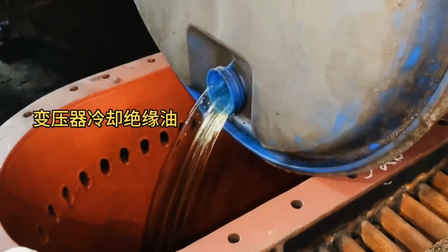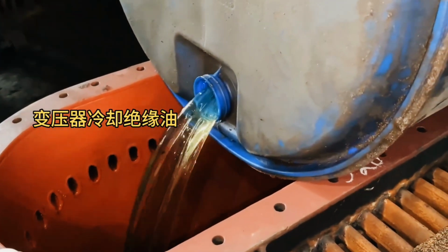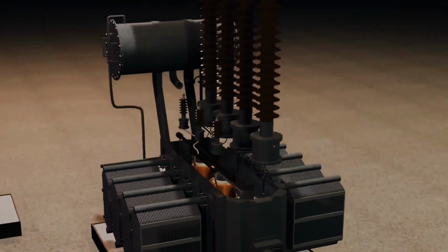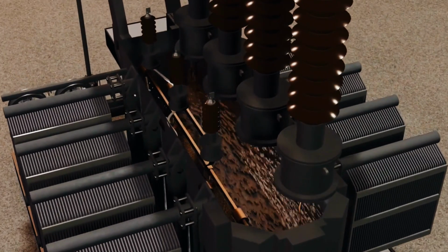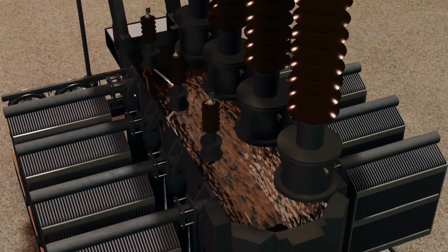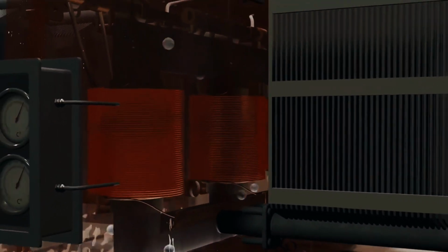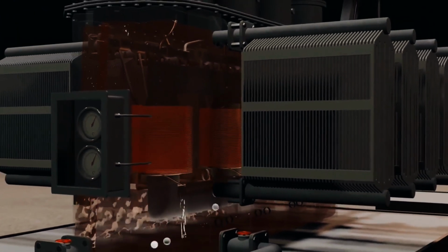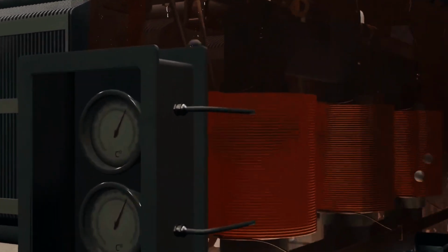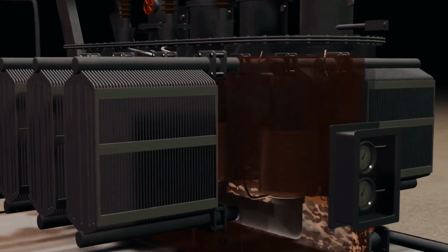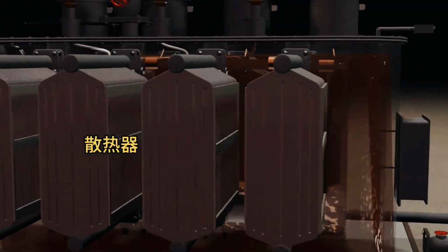Transformers generally come in two types, dry-type transformers and oil-immersed transformers. The transformer windings immersed in insulating oil can provide insulation and cooling effects. When the transformer is fully loaded, the resistance and magnetic loss generated by the windings convert into heat, causing the temperature to rise, and the insulating oil can transfer this heat to the external radiator.